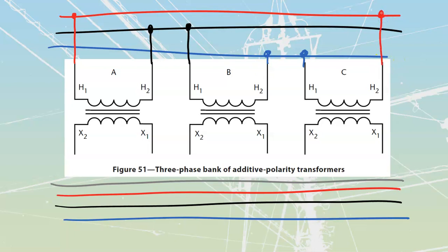Over here, we've got our standardized connection in. It's a delta one, so we just check all of our lines. And we're just going to do that real quick count. 2 connections, 2 connections, 2 connections. Therefore, this whole thing is good to go. Let's take a look at our low voltage side.